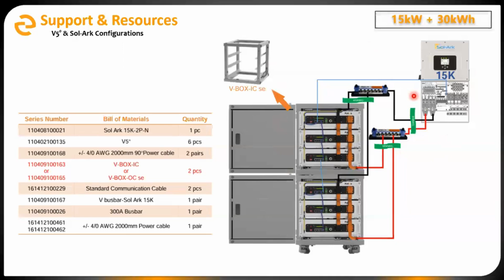Here we're using the V bus bars, so there's some flexibility here. As I was saying earlier, a lot of times you can skip these two bus bars and just use the V bus bars on the Sol-Ark. You could skip all these bus bars altogether and just run a positive and a negative from each battery cabinet directly to the inverter. Maybe the batteries are physically located a ways away from the Sol-Ark, so it makes sense to bus them at the cabinets and reduce the cable run over to the inverter. You're not locked into exactly this solution, and we can do any sort of custom design as well. So if you're doing a project and don't find what you need in our guide, just let us know and we'll be happy to help you out.